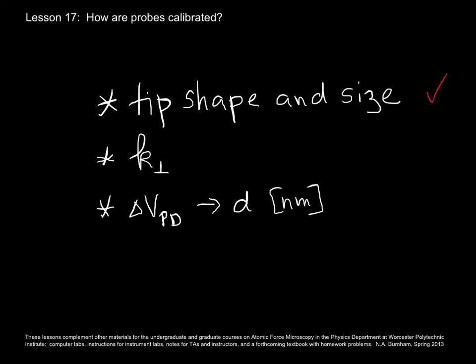In summary for this lesson, I spoke about the 4 main ways of getting your tip's shape and size, the 4 main ways of getting your normal spring constant, and the one generally accepted way of converting from photodiode voltage to deflection. And remember, in order to have a quantitative magnitude of the force, you need to have both the cantilever spring constant and the deflection calibrated.